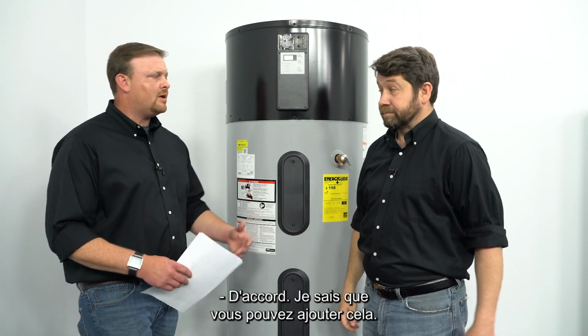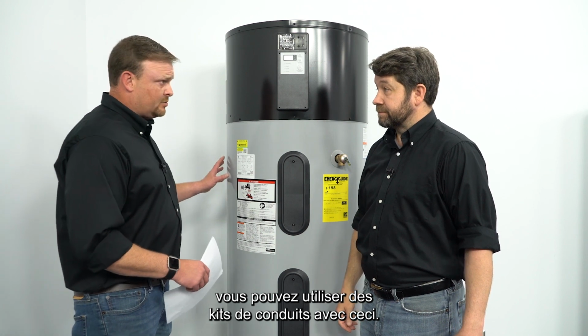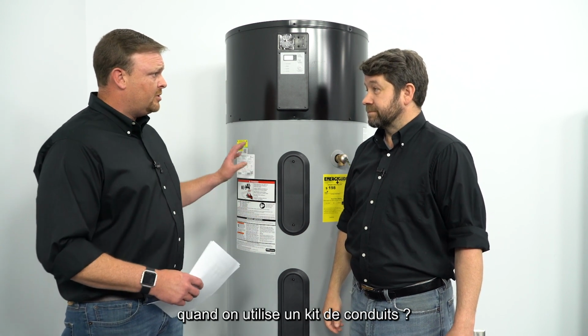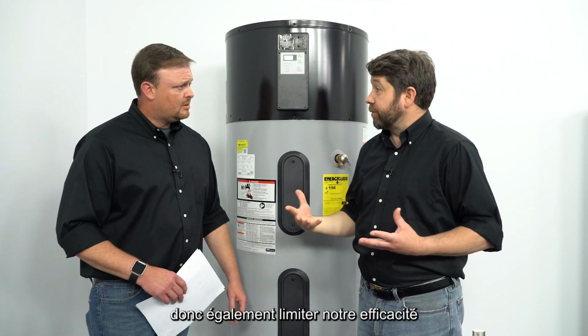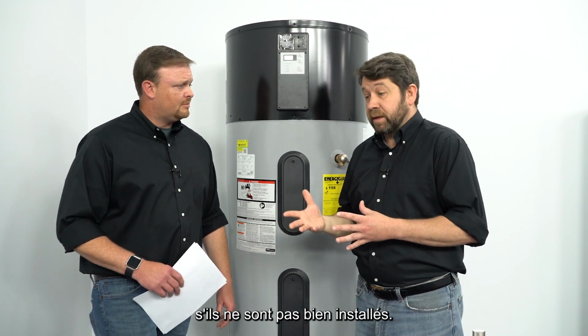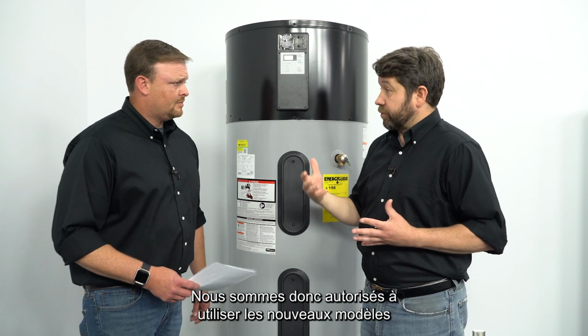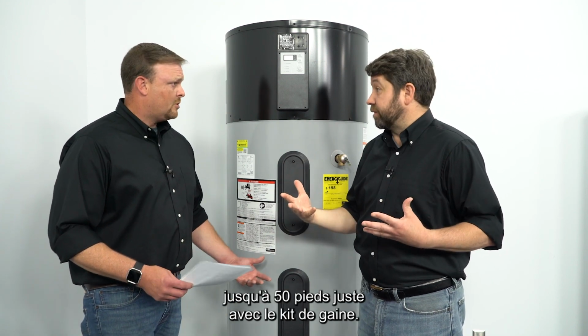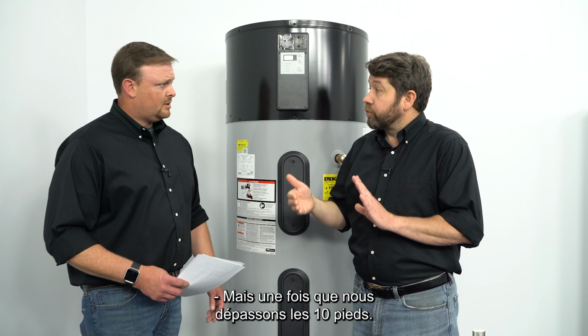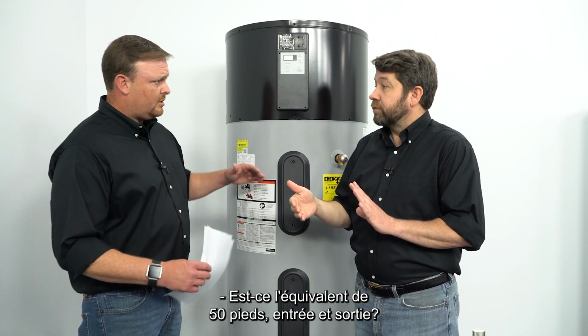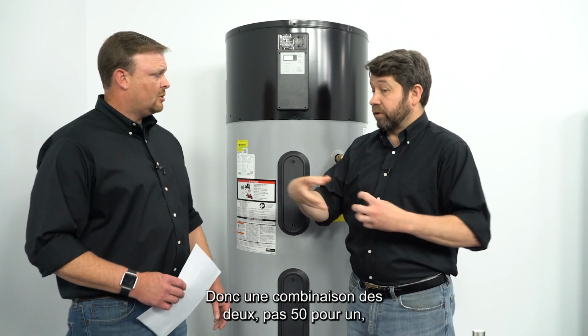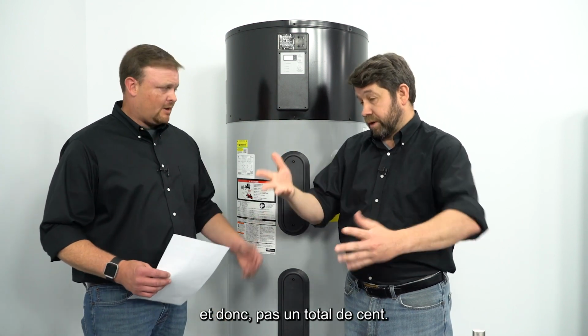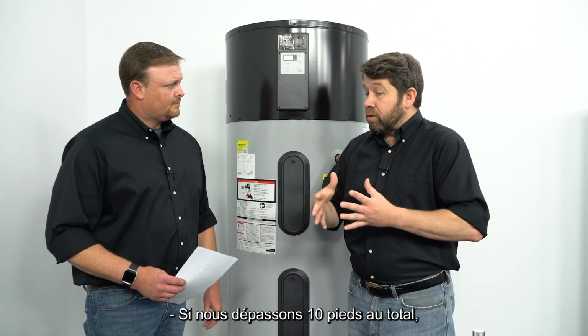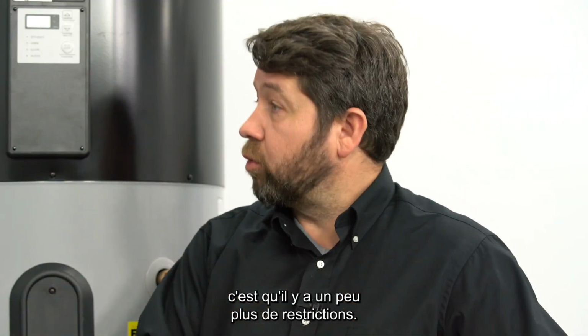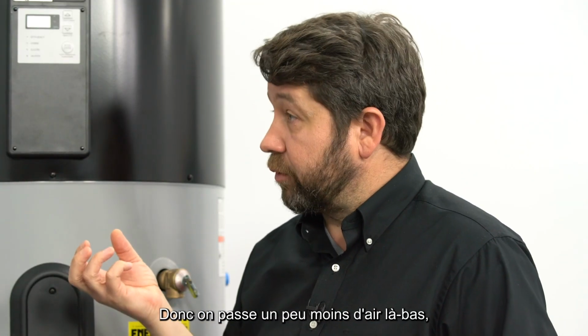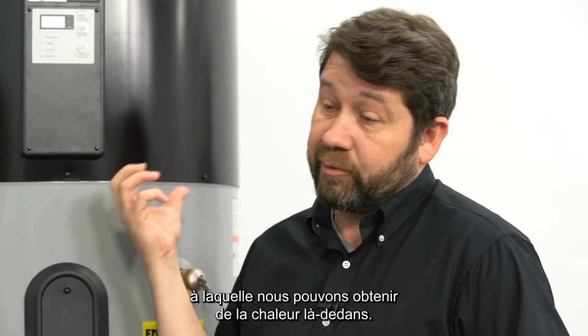Okay, what about, I know you can use duct kits with this. Is there anything we need to keep in mind when we use a duct kit? So duct kits can also limit our efficiency if they're not installed very well. We are allowed to duct with our newer models up to 50 feet just with the duct kit. Is that 50 feet equivalent, inlet and outlet? That's inlet and outlet combined, a combination of the two, not 50 for one, so a total of 100. Okay. If we go over 10 total feet, what happens is there's a little more restriction, so we're moving a little less air through there, which affects how quickly we can get heat in there.